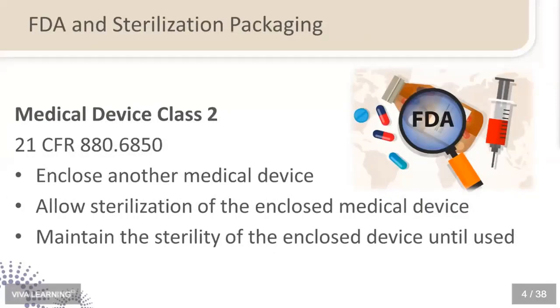We need to talk a little bit about some alphabet soup, so to speak, because the sterilization packaging is regulated by the Food and Drug Administration. It is considered, in fact, to be a medical device. It's classed as at a level 2. And the basic premise, the purpose, is it's going to be used to house or enclose another medical device, meaning our instruments. The materials have to allow for the penetration of the sterilant, whatever that may be, whether it's steam or it's dry heat or it's a vapor. The sterilant has to be able to penetrate through the materials to be able to access the enclosed instruments. And then that same material has to be able to close at the end of the cycle so that it's going to maintain the sterility of the instruments until we're ready to use them.